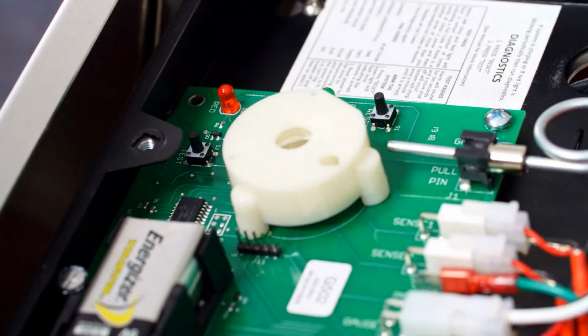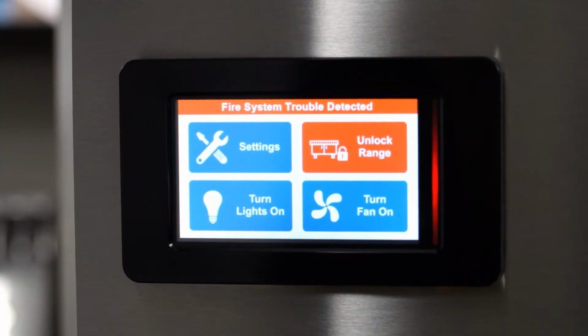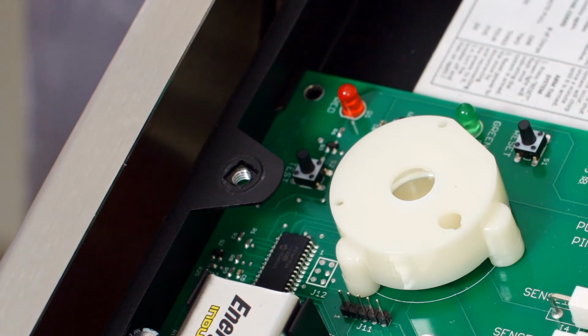Pressing then releasing the test button on the fire system control board will begin a diagnostic test, putting the system into a test mode. This is a way to identify that the system is working properly and that the range disconnect shuts off fuel to the range without discharging the fire suppression wet chemical. After the test mode sequence is started, if any particular test fails, a specific number of audible chirps will represent the failure code. There will also be a visible quick flash of the red indicator on the fire suppression control board. If multiple tests fail, then you will hear multiple series of beeps with a pause in between each to identify multiple failure codes. After failing any part of the test, the control board will return to a slowly flashing red indicator. If all 6 tests pass, the unit will enter a shut-off sequence.